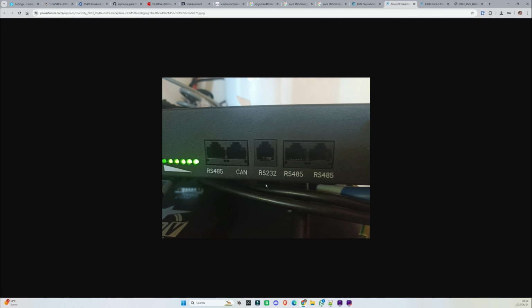This is a problem I found on the BSL batteries I use. They've got the RS485 and CAN bus connections disabled. I asked the guys from Get Off Grid to enable it for me, and they kindly did that. On some firmwares you can enable it without a password, others you'll need the password. There is a default password, but I'd be hesitant to go into the firmware and change settings unless you know exactly what you're doing. We'll go through how to do that, but I'd suggest getting your battery supplier or support guys to do it for you if possible.